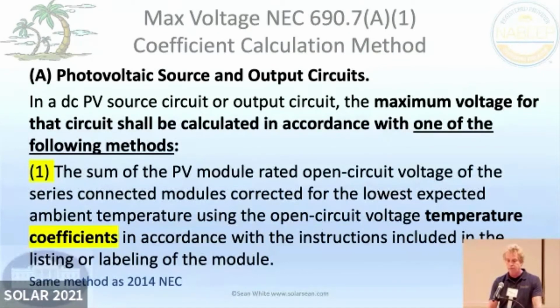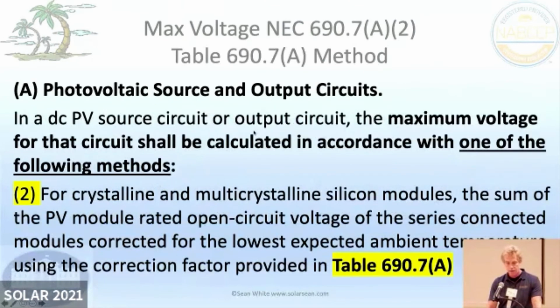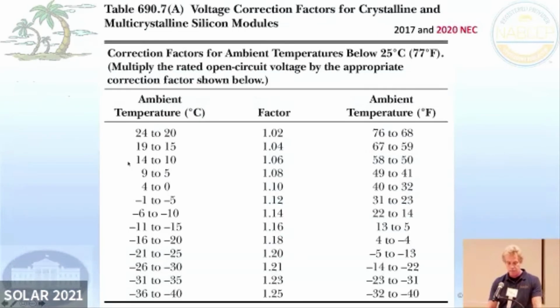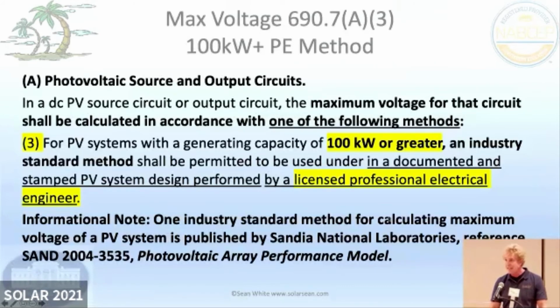So there's different ways of calculating what's your highest voltage. It's voltage based on temperature. So the first way, the way people mostly do it, is they calculate it based on math, and they use coefficients. There's another way of doing it with this table. If you went down to 10 below zero, you get a 14% increase. So you multiply times 1.14, and this is Celsius, where it's got Fahrenheit over here too. And then if you're doing something over 100 kilowatts AC output, you can do it under engineering supervision, and then your voltage can go up even higher under engineering supervision.